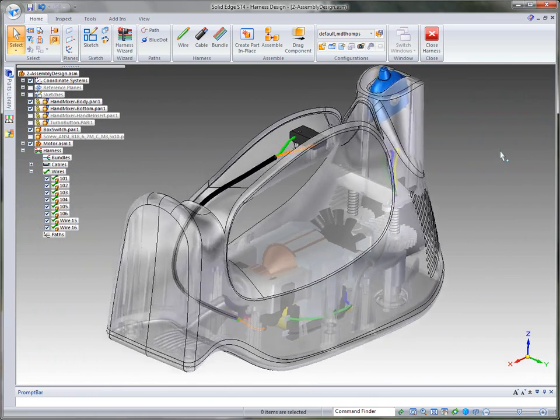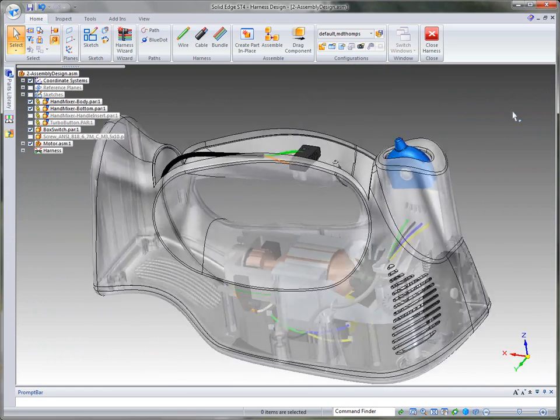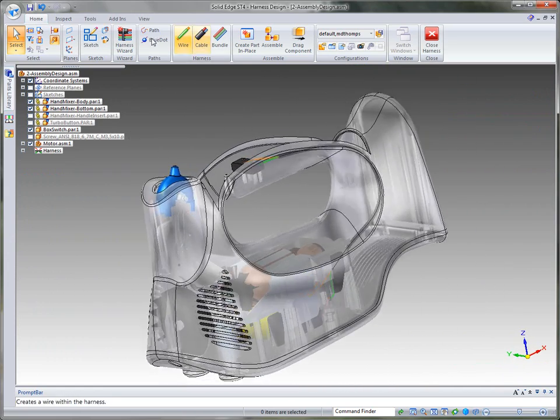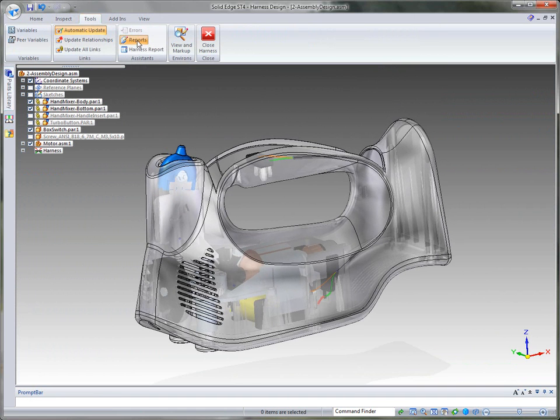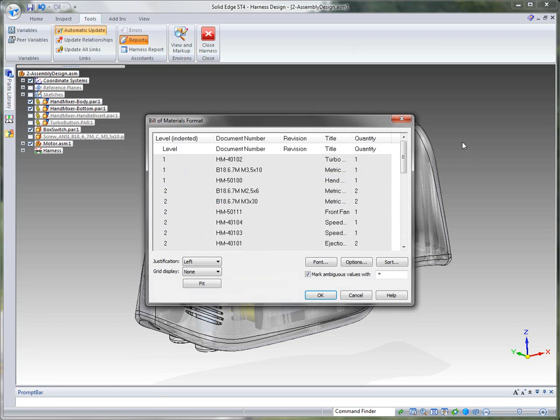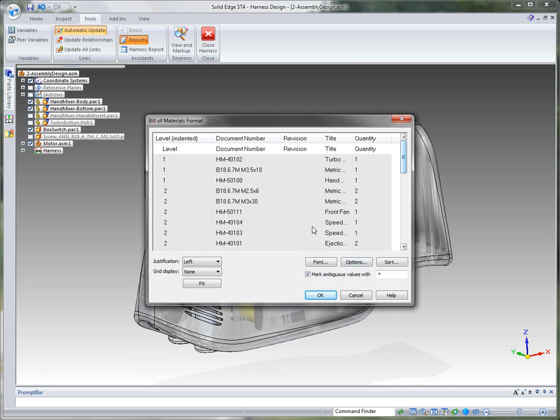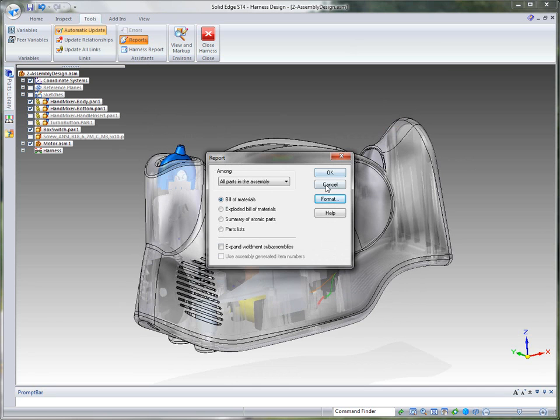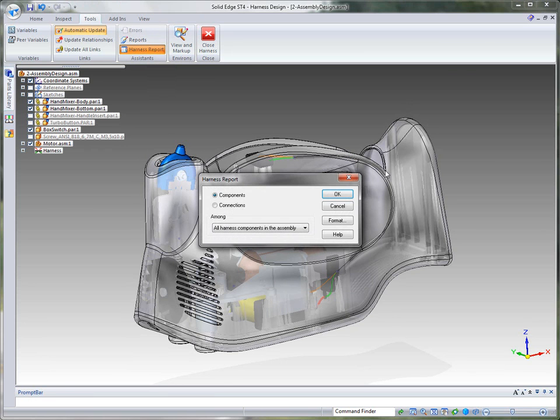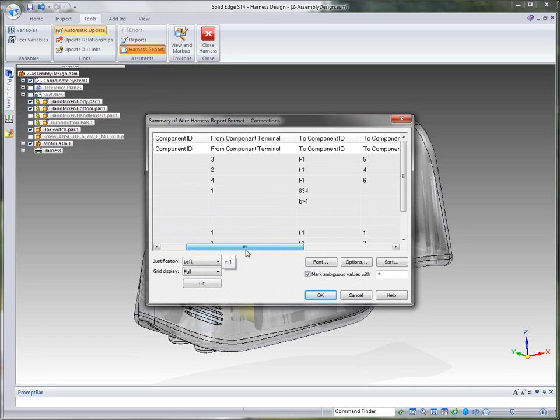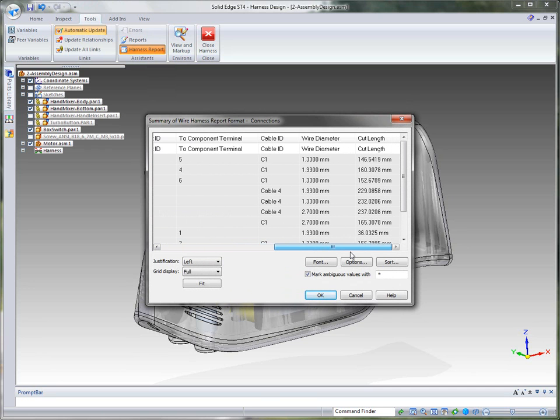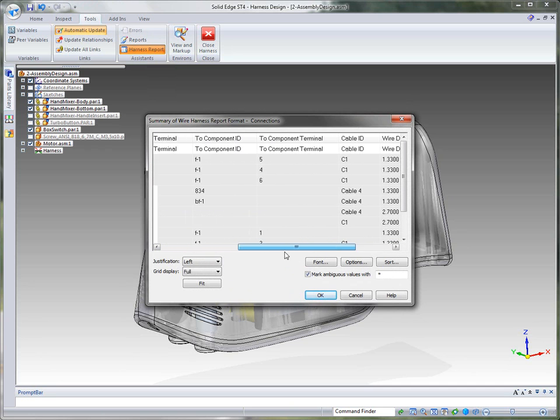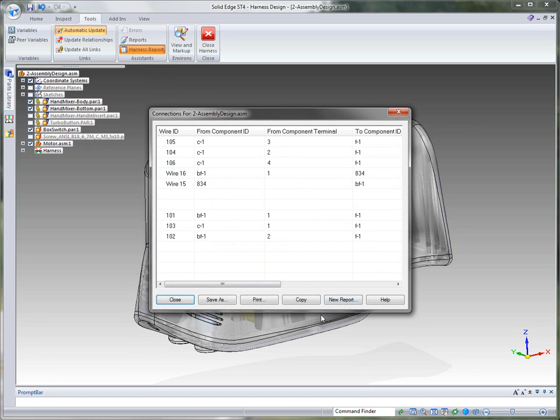Again, very easy to use, and hopefully all the tools there for you to adjust the wires as you're creating them from point to point. Another thing that I think to finish this demo up is to talk just a second about the reports. When you're generating reports, you can generate a bill of materials. And if you do, for example, format, it shows that you can do bill of materials for all of the components in this particular part. But more importantly, if we come out, you'll notice as not only a bill of materials, you can do a harness report where you can do a report on the components and the connections. So if we take a look at maybe the connections, you'll notice it gives you the wire ID, the from to terminals and component IDs, the wire diameter and the actual cut length of the wires. All of this information can be read into the draft document as well.